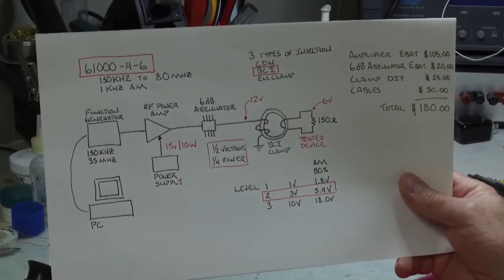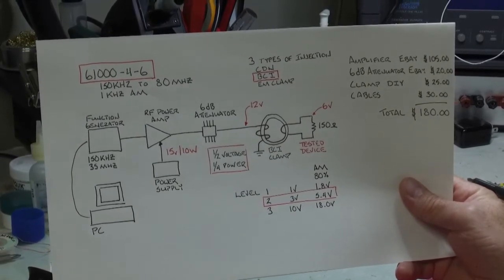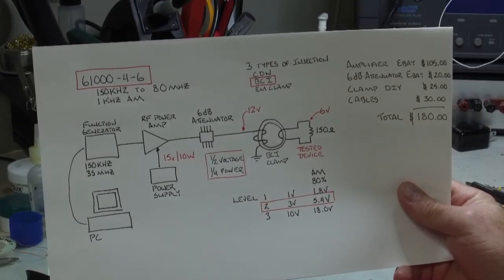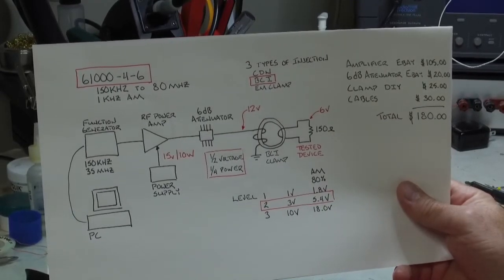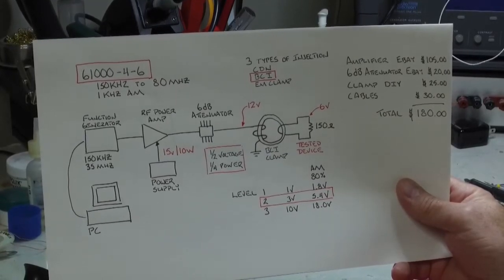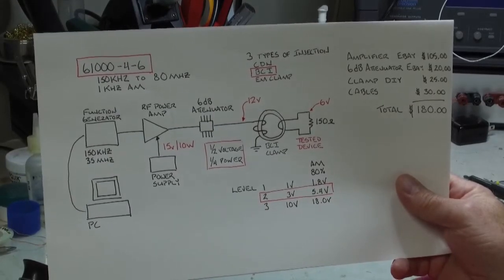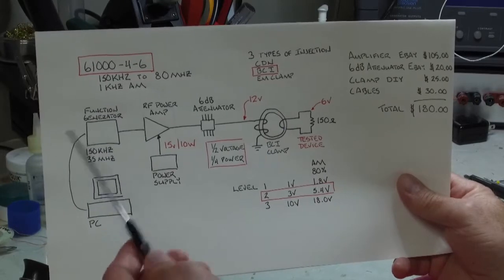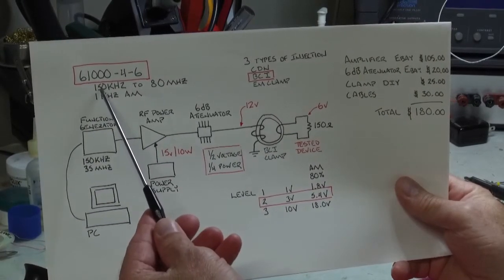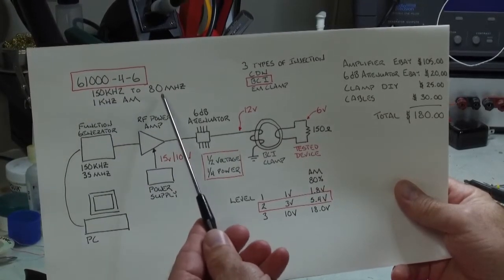Here is the block diagram of the conducted immunity test. I probably need to state that I would not call myself an expert with this system, but I have gone through this test probably a couple of dozen times at some local compliance labs. The setup basically consists of a function generator and this function generator needs to be able to sweep the range between 150 kilohertz to 80 megahertz.